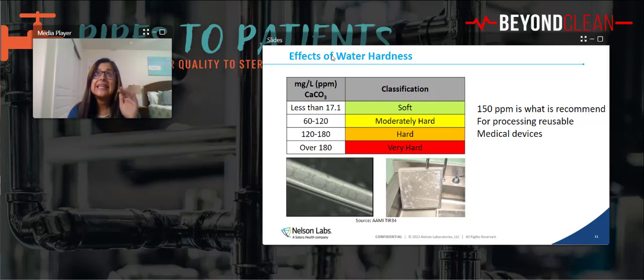We're going in visually, turning the spray arms to make sure that there is no hard water scale buildup in those little tiny holes that they have. Because if there is, we're not going to get it cleaned, right? So we want to make sure all those checks are there. And descaling: there are many detergents out there that descale the washer, so they don't have these heavy, chalky materials, if you know what I'm talking about, on the bottom and the sides of the walls.